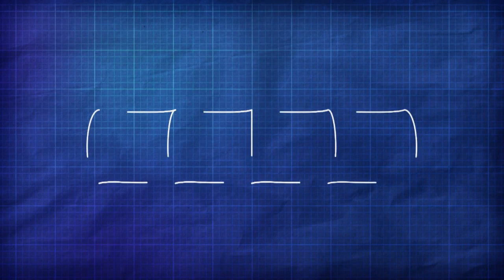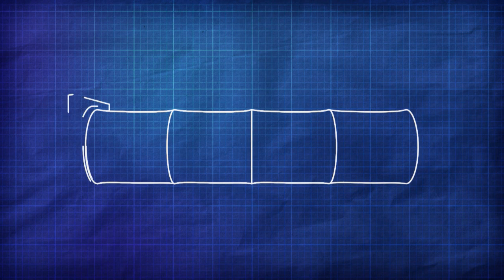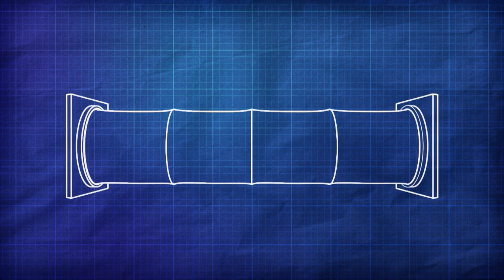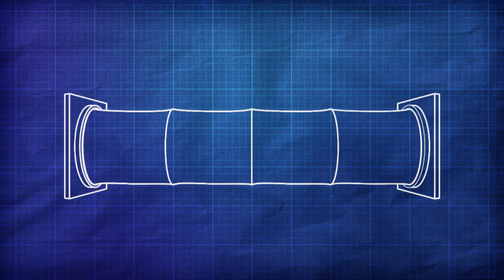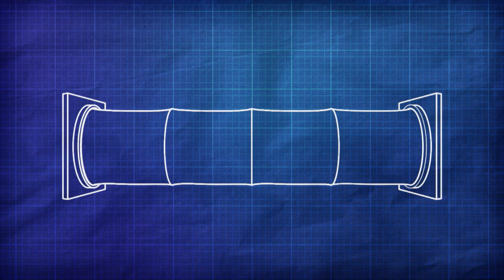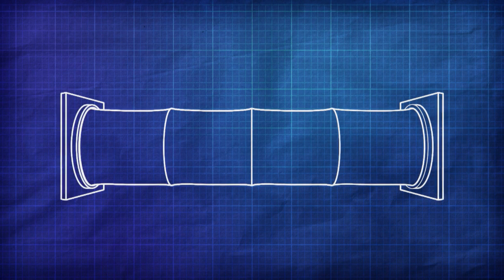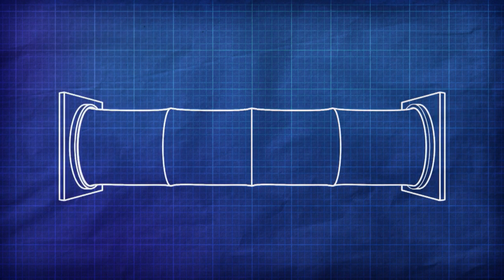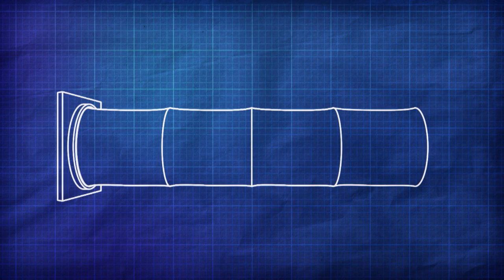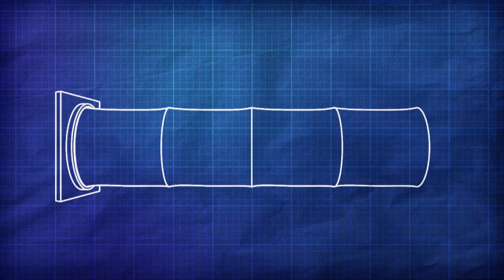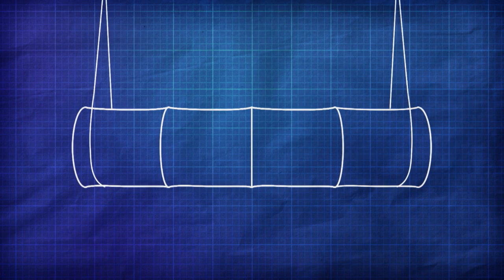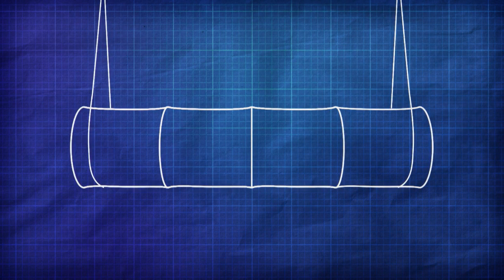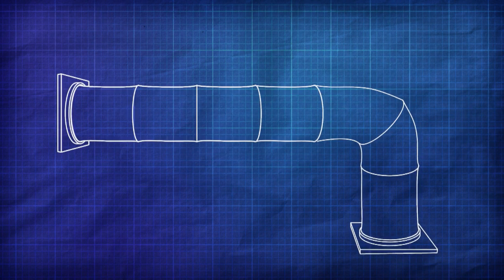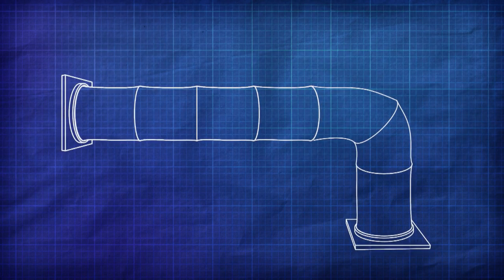Typically, a duct run is attached to some rigid object at one or both ends of the run. But some layouts force sections of a duct to stand freely, which could cause lateral swinging. Examples of such a layout include a duct that is cantilevered outward and only anchored at one end, the freestanding center of a long duct, or a 90-degree angle of duct only anchored at the ends.